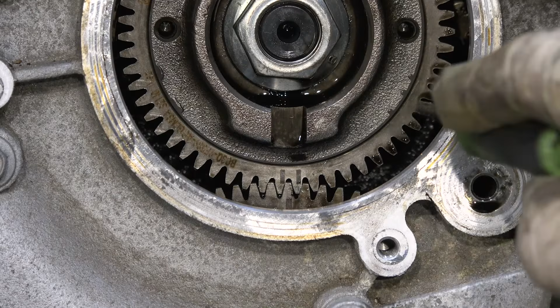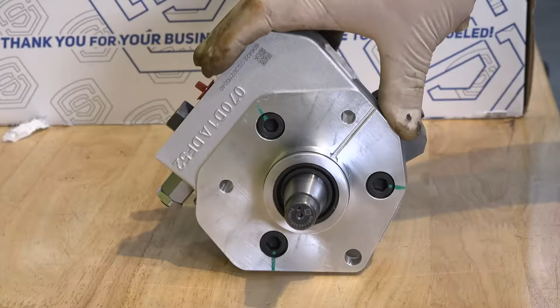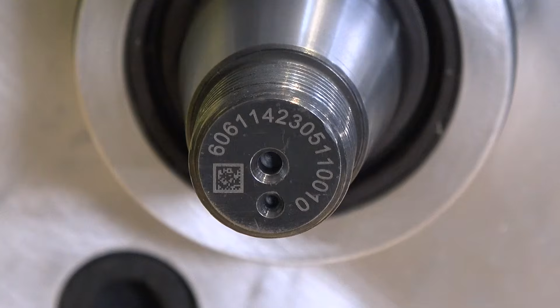One thing worth noting is that we experimented with multiple clocking positions to find what we consider to be the optimal timing to reduce vibration and harmonics. That's why we recommend timing the DCR. If, let's say, the DCR isn't timed for some reason, the pump isn't going to self-destruct. The main reason for timing the DCR is to reduce the vibration and the gear noise. Now, what are some of the most common issues that you guys see with the DCR pump?